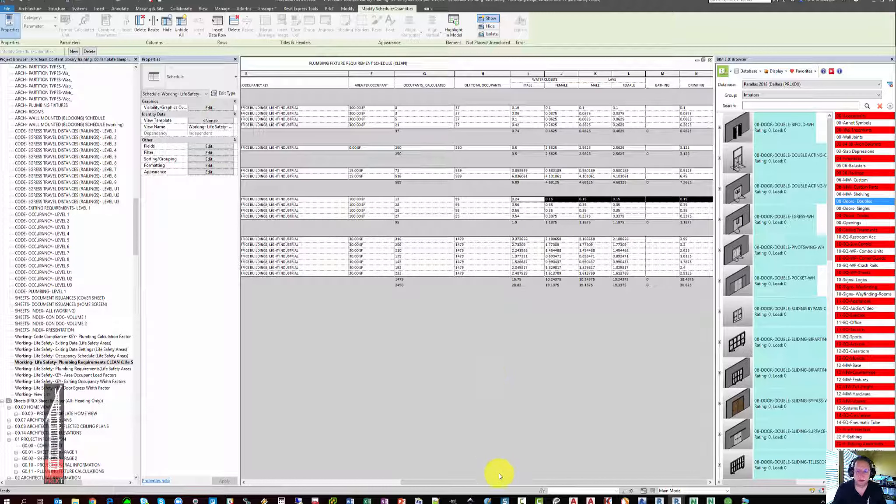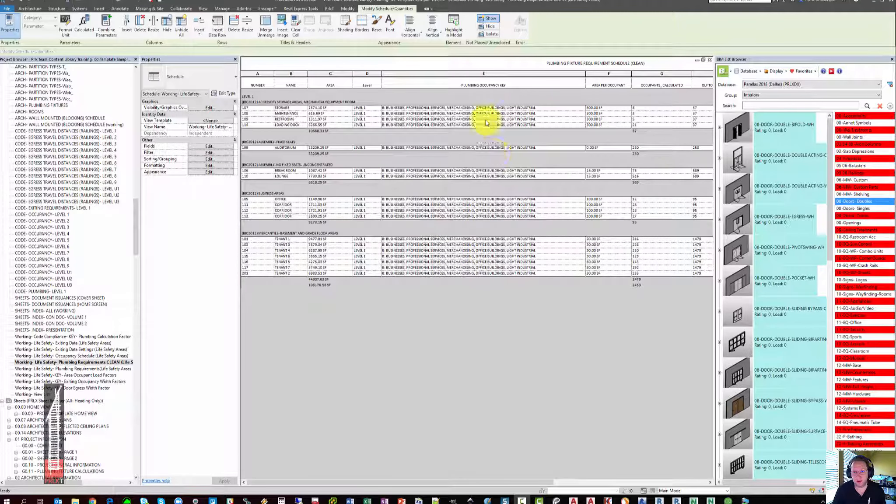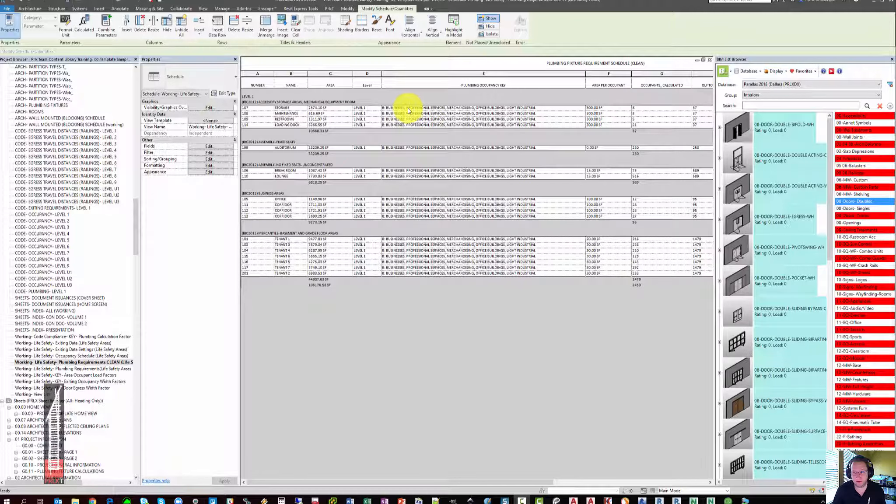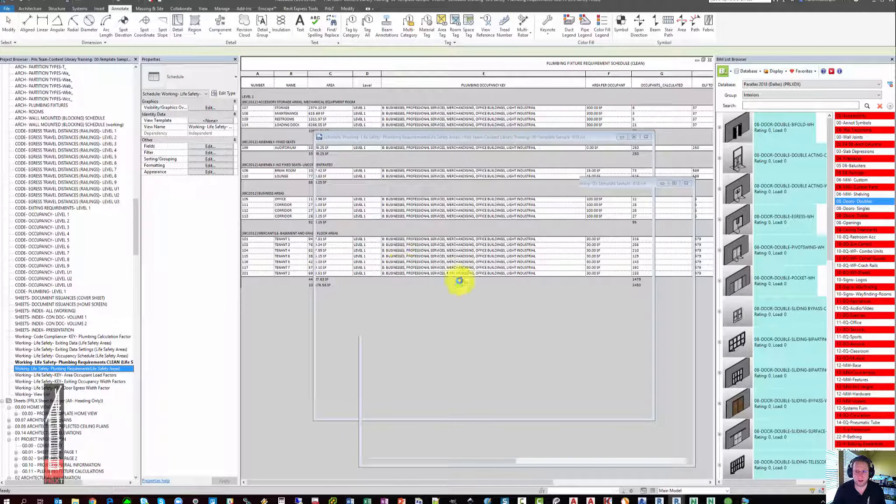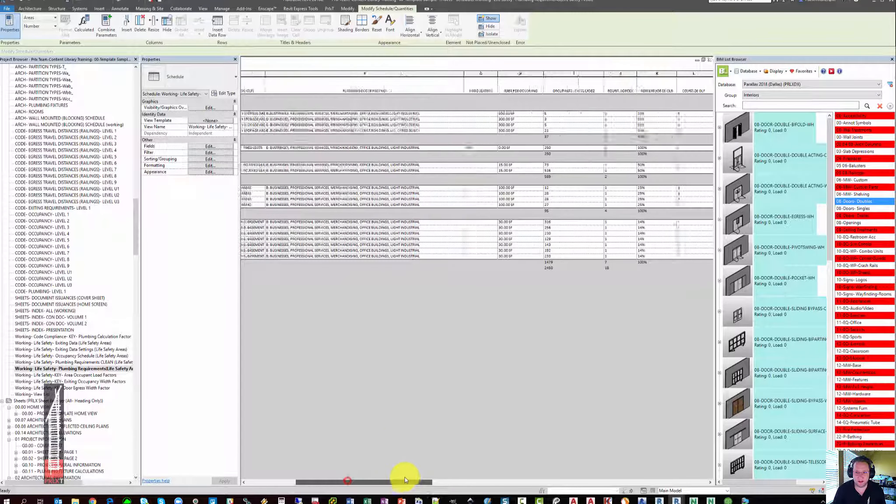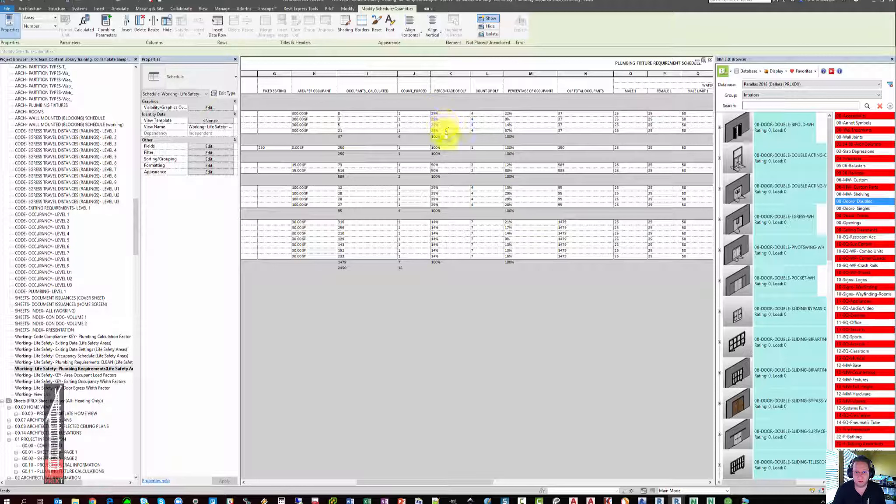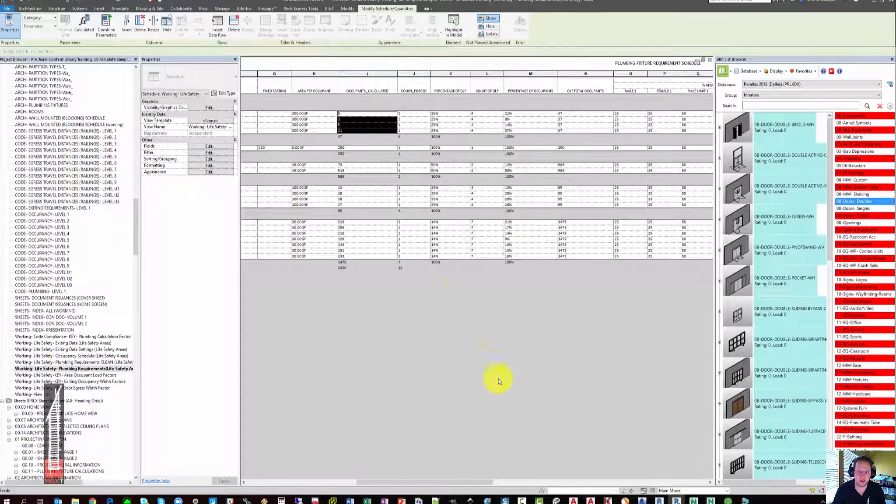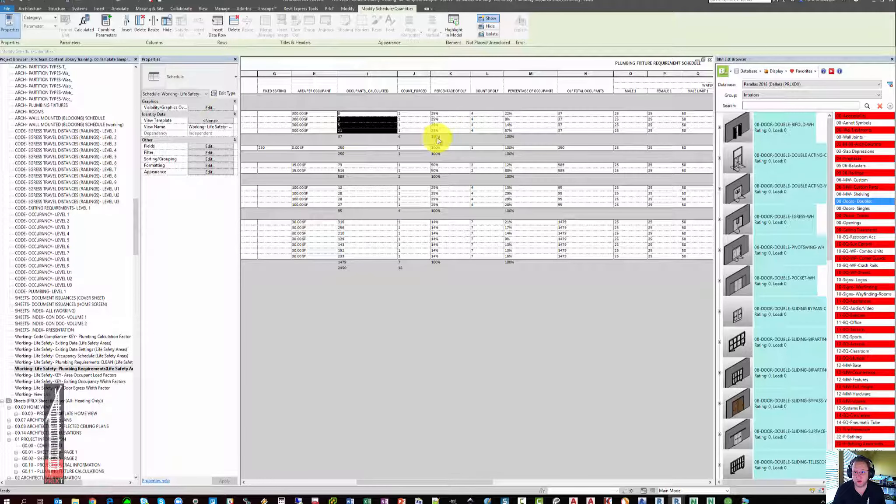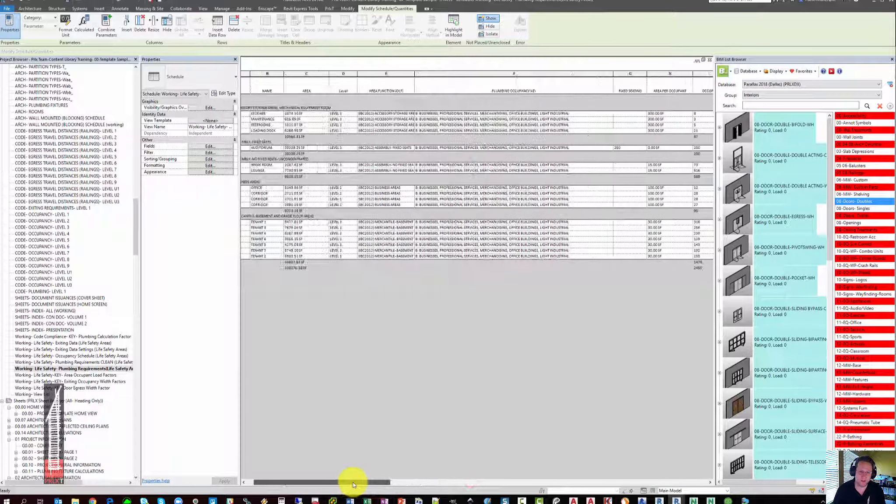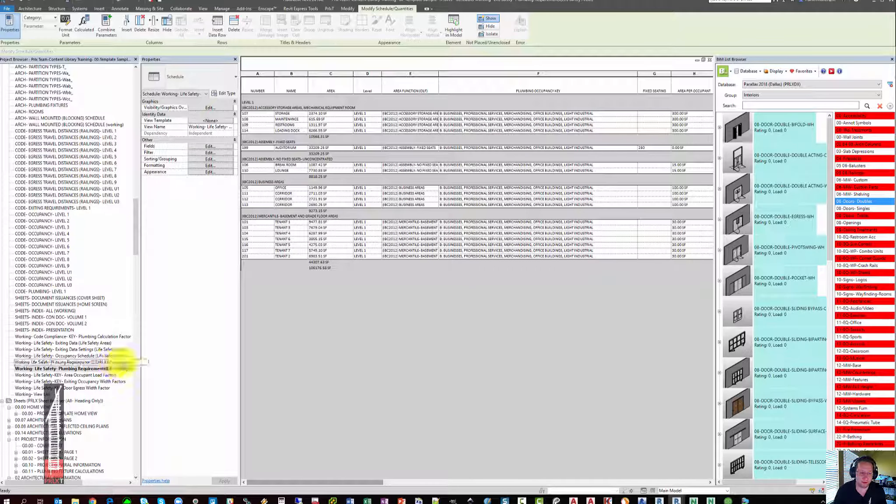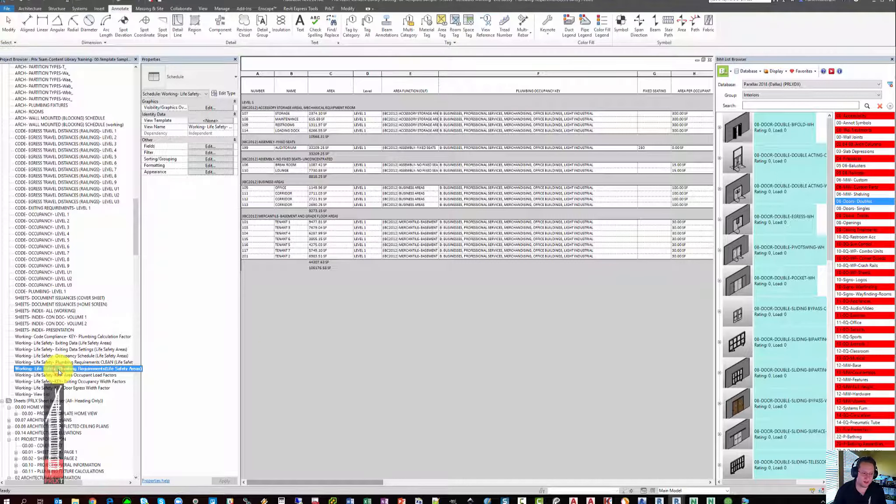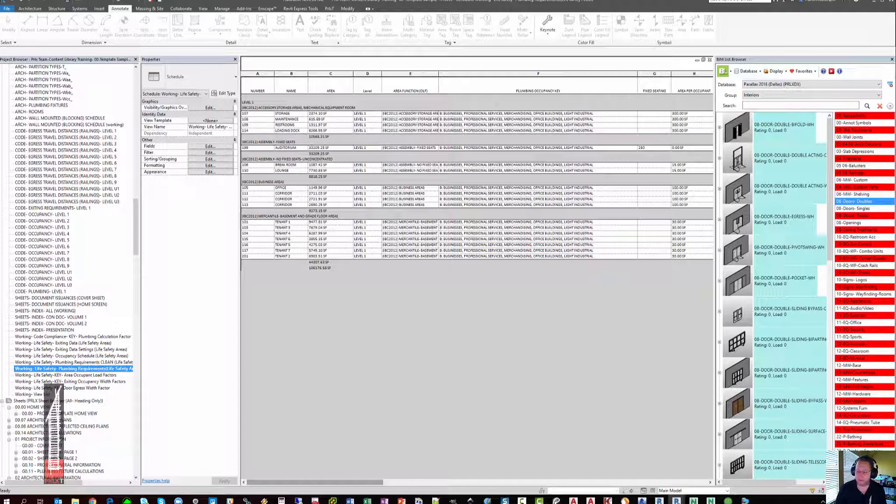which can greatly exacerbate how inaccurate the totals of the schedules are. For this reason, I keep them all unrounded. Because of how the code is written for business occupancies, if you were to go to the other plumbing fixture schedule, you will simply see that this schedule has a lot of specific math going on where we're basically calculating the occupancy of each classification as a total, and then performing the IBC calculations on that, and then dividing it back down into where the percentage of occupants go. This is pivotal for getting IBC plumbing requirements to work correctly inside Revit. Therefore, that's all this extra schedule is doing here, is exposing all of that math in case you would like to double check it yourself.